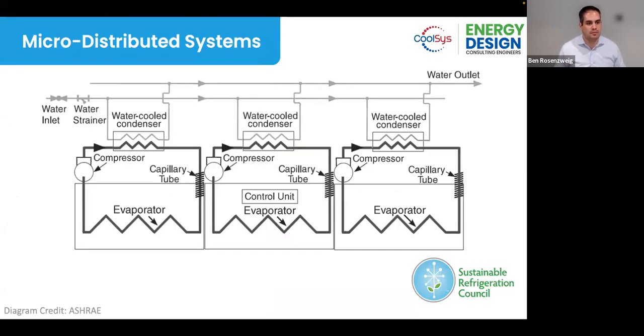Next slide, please. Now we'll talk about micro distributed systems, and we'll focus a little bit more on this for the rest of the conversation. And this here simply is a very simple diagram of what a micro distributed system might look like from a flow perspective, where you have, say, 3 refrigerated cases next to each other that are each served by individual compressor systems that sometimes have just one compressor in them, serving one evaporator, using capillary tubes for refrigerant flow control or other control methods. And these can be air and water cooled.